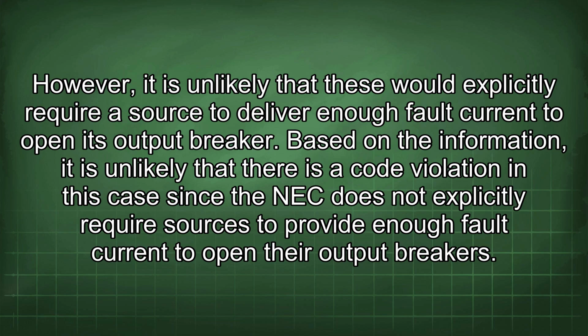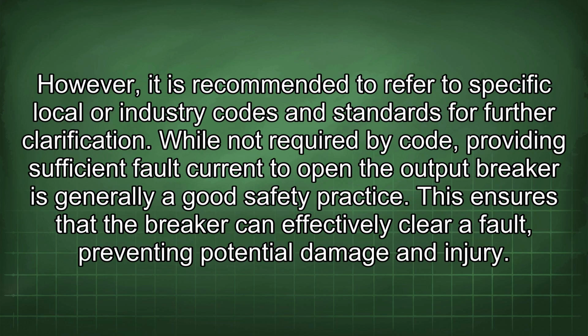Based on the information, it is unlikely that there is a code violation in this case, since the NEC does not explicitly require sources to provide enough fault current to open their output breakers. However, it is recommended to refer to specific local or industry codes and standards for further clarification. While not required by code, providing sufficient fault current to open the output breaker is generally a good safety practice. This ensures that the breaker can effectively clear a fault, preventing potential damage and injury.